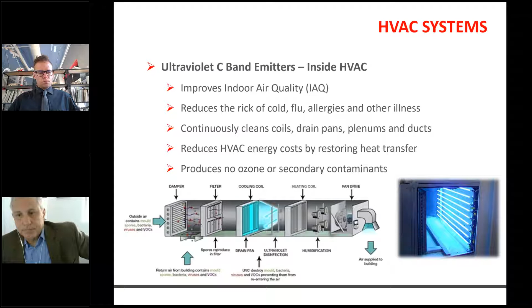Historically, UVC is installed downstream of the chilled water coil, to keep the coil and the pans clean, and also to help with indoor air quality as well. UVC works best with static surfaces, not as well with moving air streams. So it's not as good an option as some other things, but it does help. Next slide.